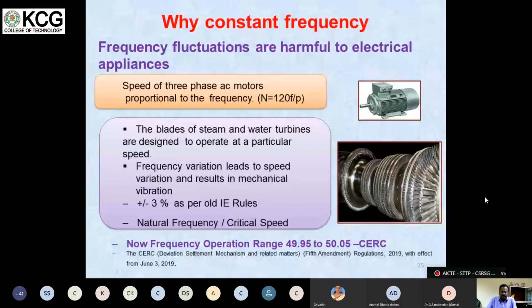When we operate the region with a higher frequency, we are simply wasting our energy. There is no higher frequency required in the system, but we are injecting more power, or injecting more fuel, to have higher frequency. It is a waste of energy. So we have to maintain within 49.95 and 50.05. Plus or minus 3% is like a student getting the pass mark, and 49.95 to 50.05 is like a person getting first class with distinction. So it can be operated, but should be operated. This is grid discipline. It should be operated within this narrow range only, as per regulations.